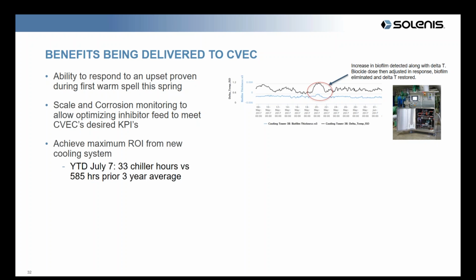It's really helpful to have that real-time data available to you. Otherwise, you're putting corrosion coupons or similar devices in place and leaving them for 30, 60, or 90 days of exposure to get relevant results. You don't want to take them out too soon because they're not acclimated to the chemistries you're using. So with corrosion coupons, you've got to wait a fair period of time, maybe 2 or 3 months, before you have good data you can use. You're kind of running blind for a period of time.